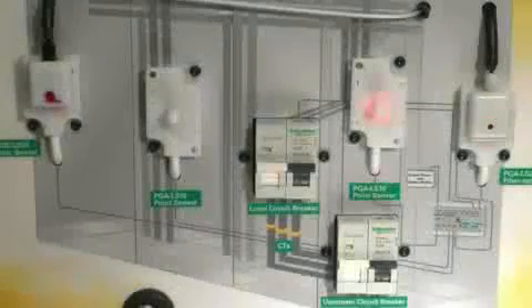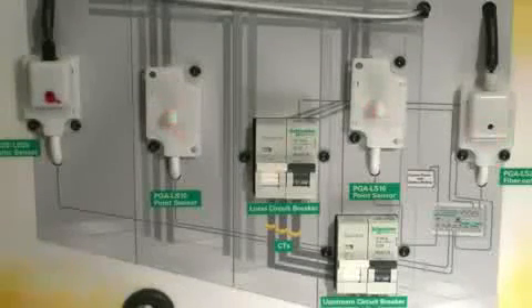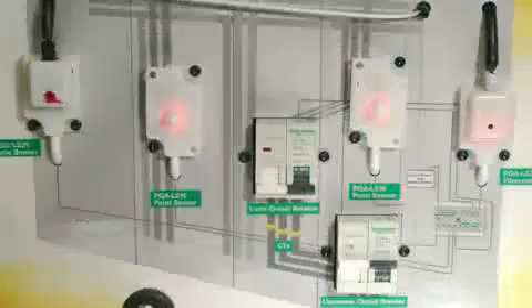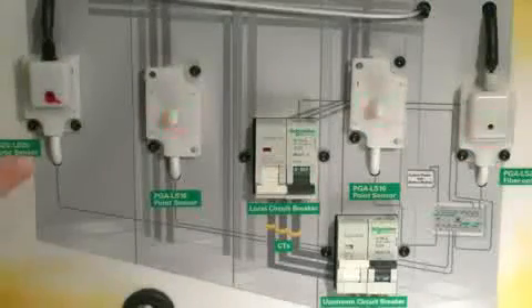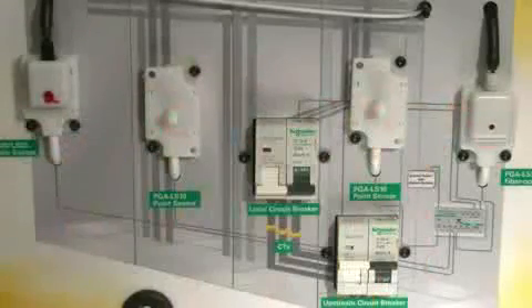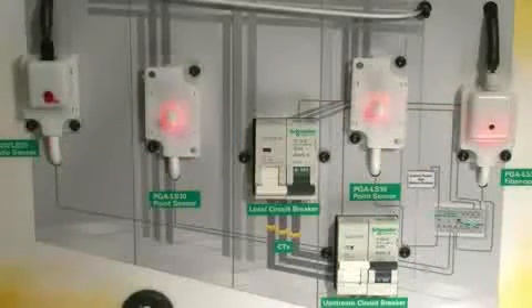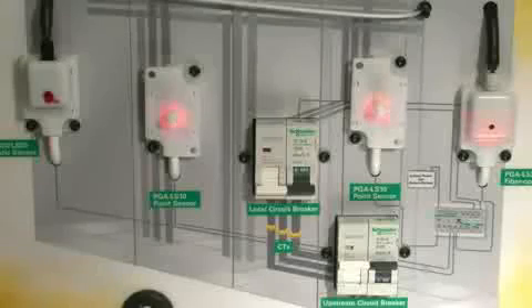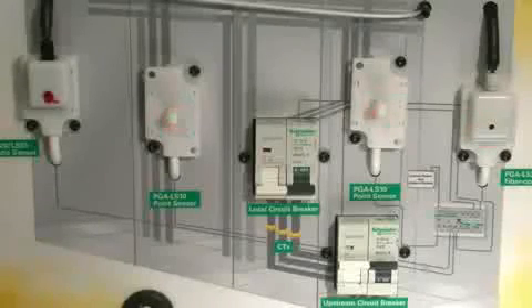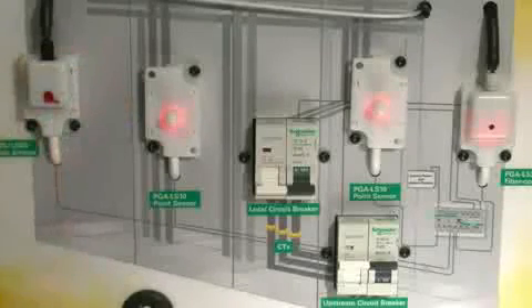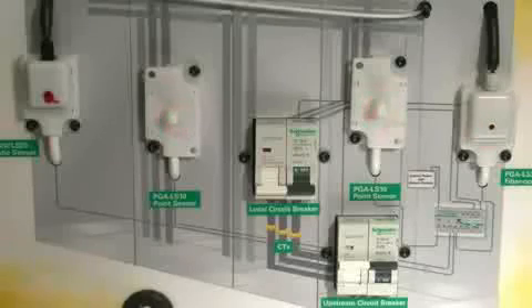When an arc flash occurs and the light is seen, and I'll demonstrate that with this camera flash, the sensors change status. As you can see here, every sensor saw the flash. But if this were a divided cabinet and everything is dark, but you're running the relay off of a battery backup control power, you would still see which sensor had the fault, so you would know which cabinet the fault was located in, even in the dark.